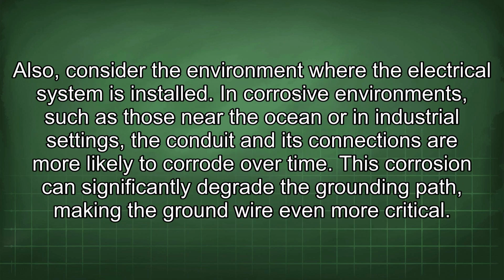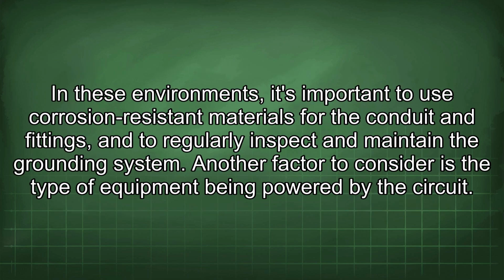Also, consider the environment where the electrical system is installed. In corrosive environments such as those near the ocean or in industrial settings, the conduit and its connections are more likely to corrode over time. This corrosion can significantly degrade the grounding path, making the ground wire even more critical. In these environments, it's important to use corrosion-resistant materials for the conduit and fittings, and to regularly inspect and maintain the grounding system.